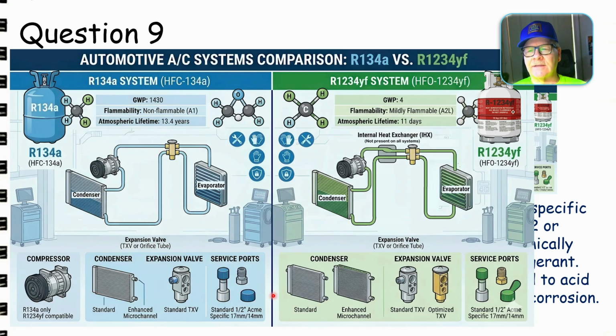So you've got some nice little stuff down here you can look at. You might notice in these drawings the absence of a receiver dryer. The reason it's absent is because it's built into the end of the condenser, because that's actually a subcooler. Whenever the refrigerant goes from the discharge line into the subcooler, it goes through this dryer, and then through the lower part, which is separate from the upper part, and that cools the liquid refrigerant.